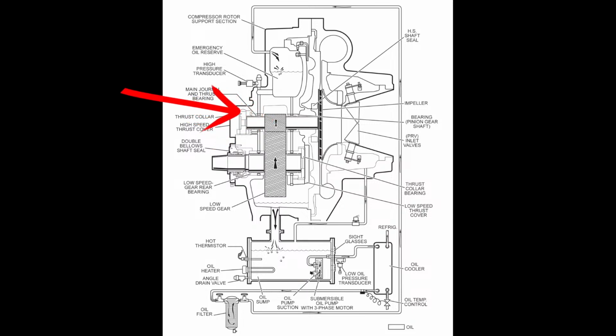So our sensor is right here. Our D housing sits right about here and right about down here. The big housing that the coupling sits in, that the motor shaft is also inserted into with our coupling here. So this is where you're inside of that D housing, and this is the high speed cover, which is the thrust collar cover. So the proximity probe itself sits right here. It's sending out these pulses, and what it's monitoring is the actual thrust collar distance itself.